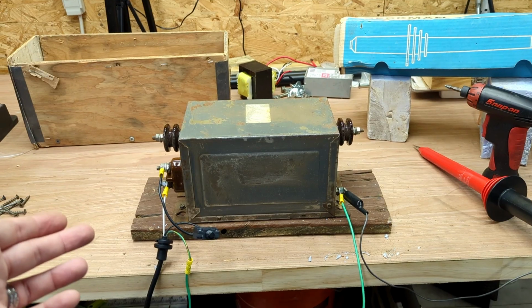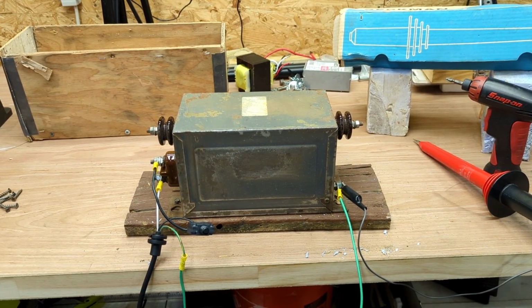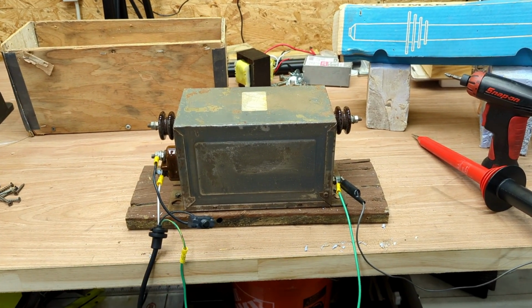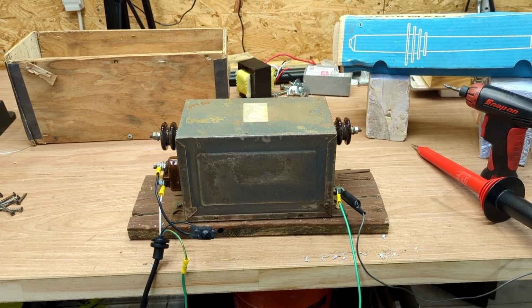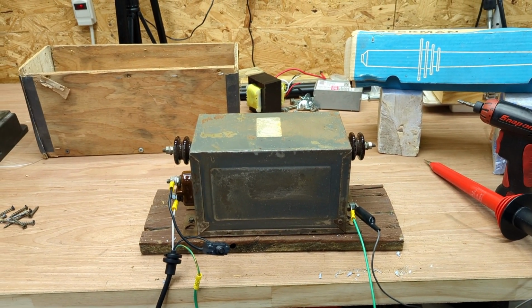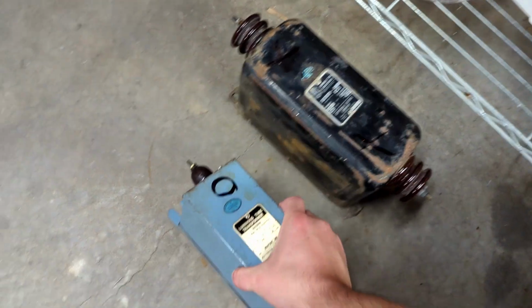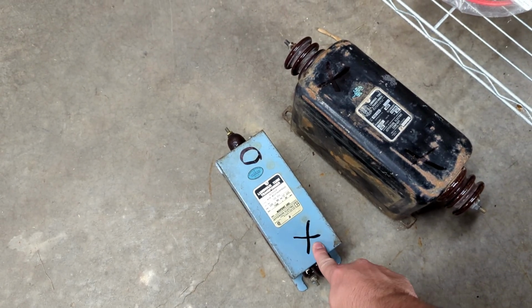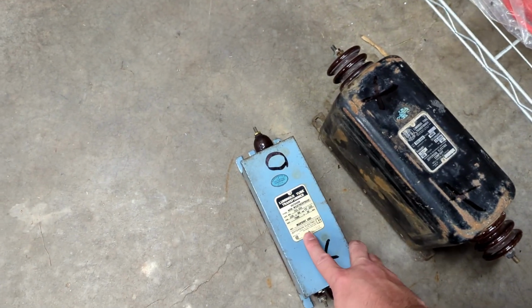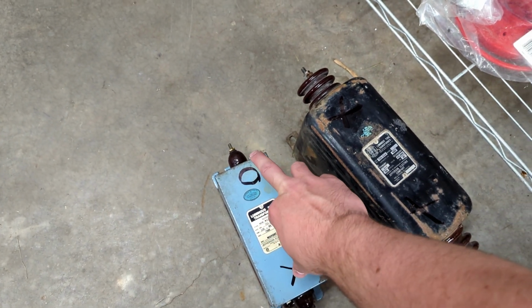You can have varying voltages if the windings on it are shorted or have some kind of issue. They can still work if shorted to some extent. They're just going to have the wrong voltage and it won't put out the right current. In fact, I have some examples. The deal was too good to be true on eBay. This one, unfortunately, was only 30 or 40 bucks, and it's got one good side and one bad. This was 7.5 kV, so that's both together. So divide by 2, it's basically useless.